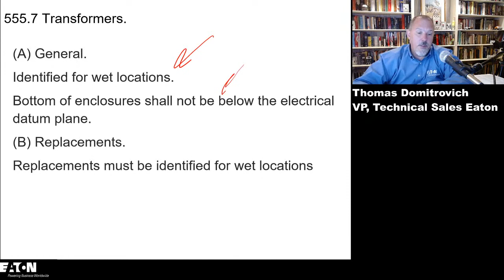And in this requirement from a transformer perspective, we said, you know, you can put transformers out there. They have to be identified for wet locations. We didn't say listed for wet locations because I don't know that you can buy a transformer listed for a wet location unless it's in an enclosure, right? And then the enclosure is listed for wet locations. So I think that they can be identified for wet locations. And the bottom shall not be below the electrical datum plane.